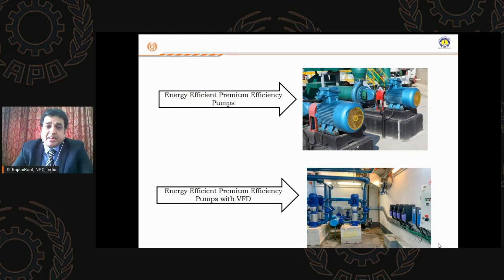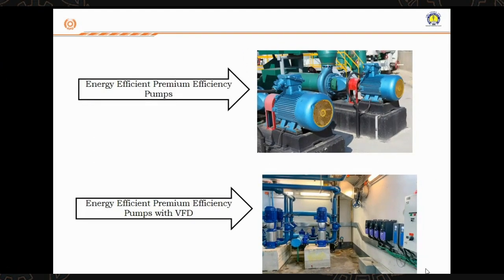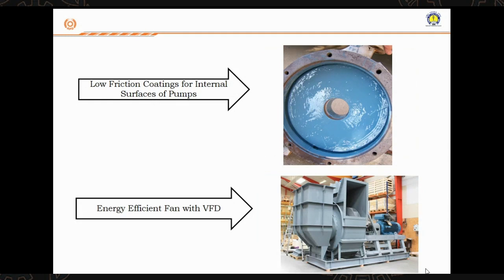And a detailed study can be conducted by an SME to arrive at whether the pump is overrating or underrating. A clear study can be conducted. Now, for the pumps itself, you have various coatings that are available. The internal coatings reduce the internal friction as the flow goes from the impeller eye to your volute. To reduce this friction, there are so many coatings available. This itself proves that around 0.5 to 1% of the efficiency will improve because of this reduction of frictional losses by having these polymer coatings inside the pump.